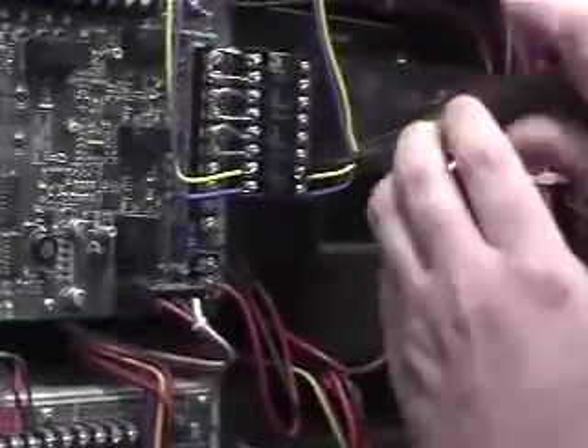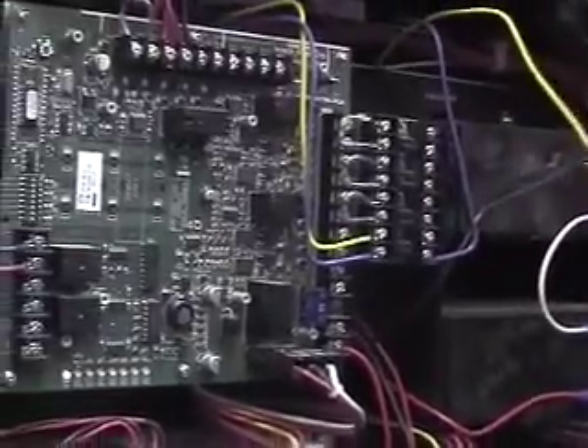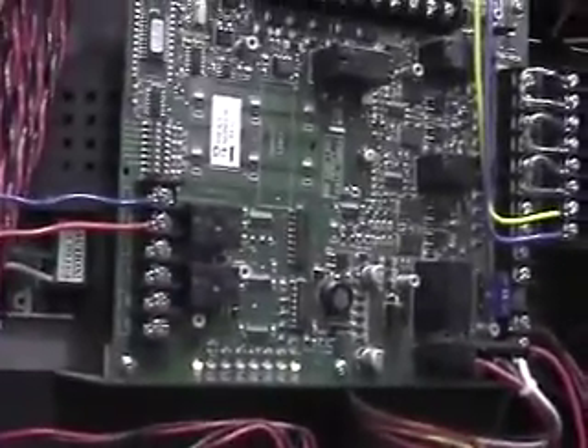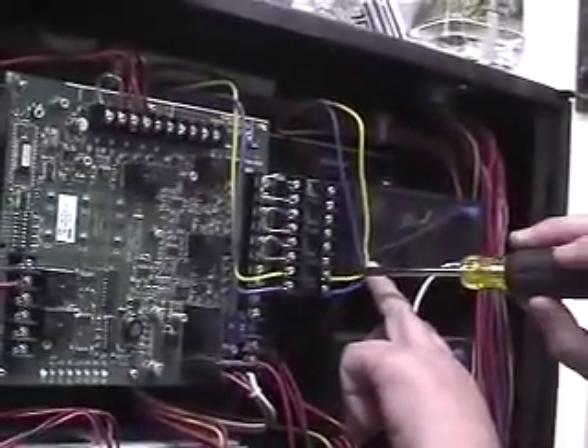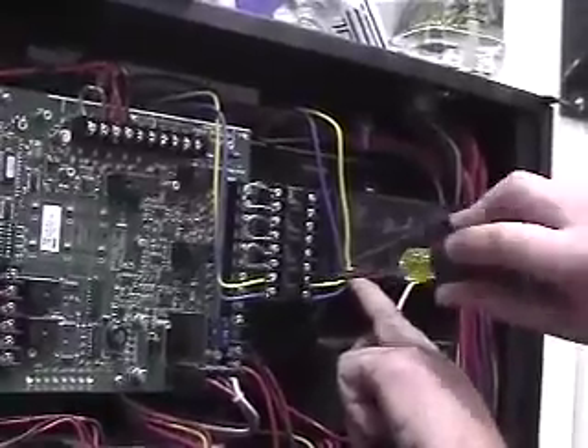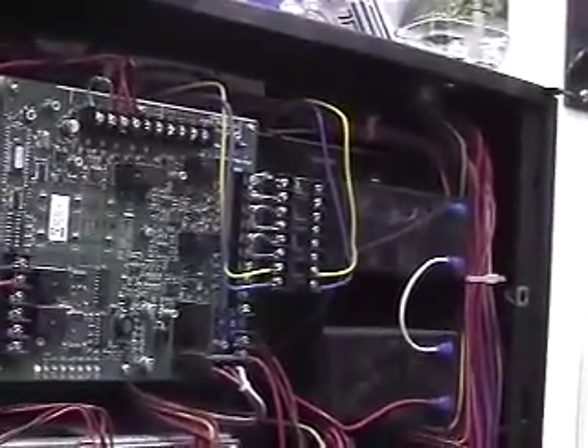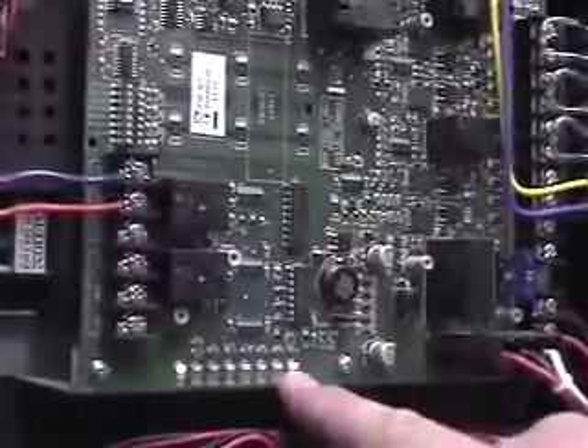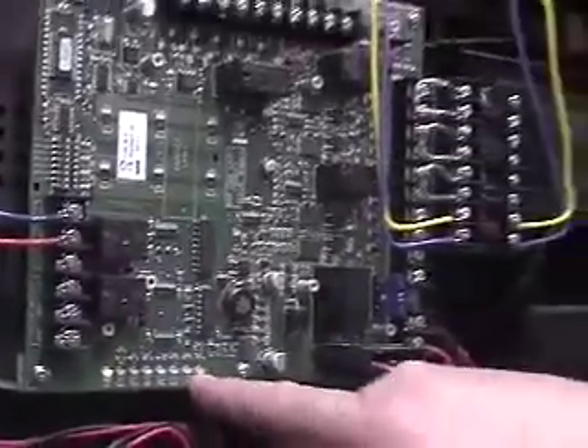Once the circuit goes into trouble, it'll come in and go solid, and then the panel will tell you that this floor transponder is in fault. Once it clears, the fault will clear, but this circuit blinks. That's saying that circuit was in fault at one point in time. So it kind of helps you know what's going on if you have an intermittent fault. But it only does it on the circuits. So ground fault, battery fault, it won't do that.